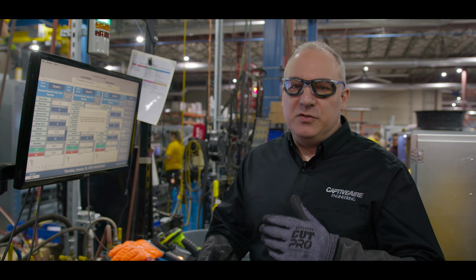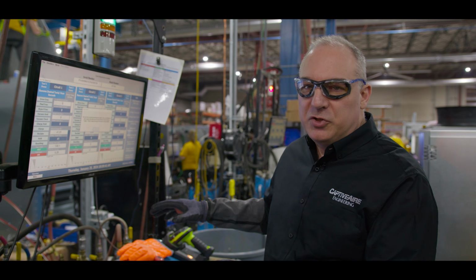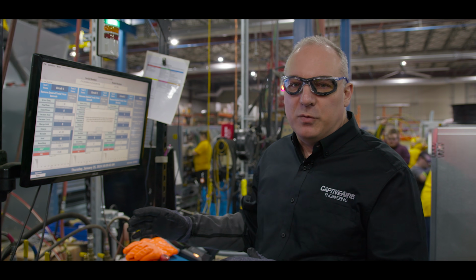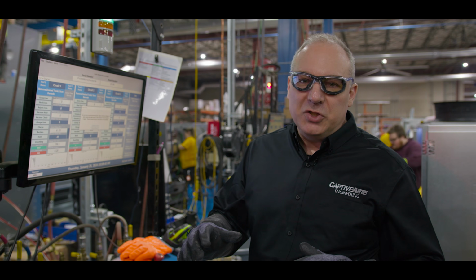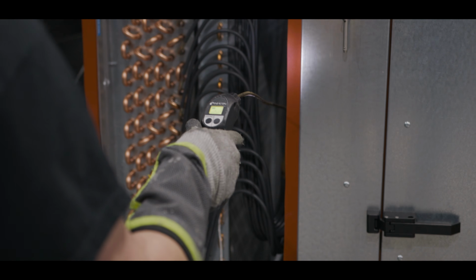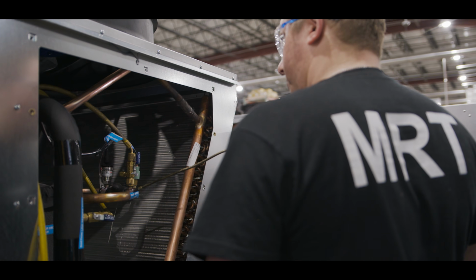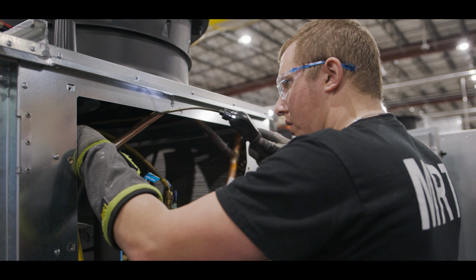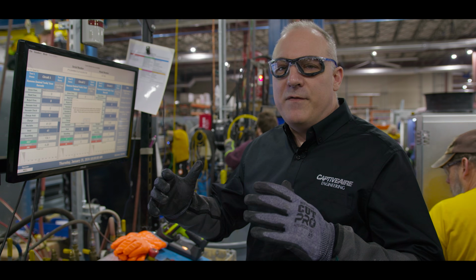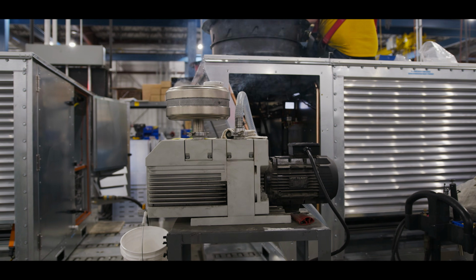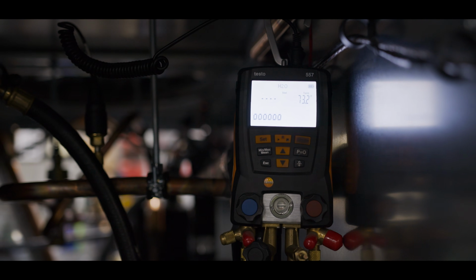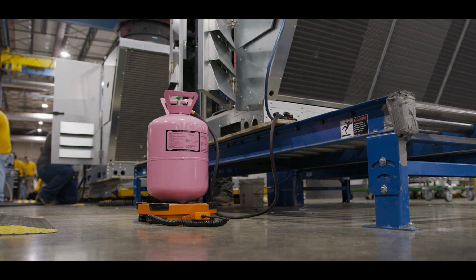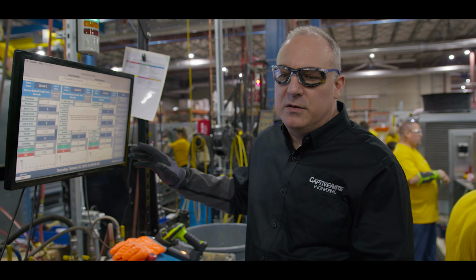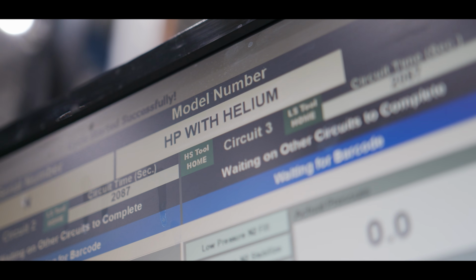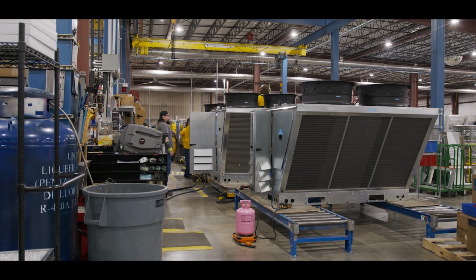We use these to vacuum our equipment down, check for leaks, high pressure checks for structural issues with piping, medium pressure, we inject a tracer gas, helium, and we look for small leaks in the copper tubing. And then once it passes all that, we evacuate the system down to a 500 micron level before we fill it with refrigerant. And this equipment has programs in it for each specific unit to make sure that we do that correctly.